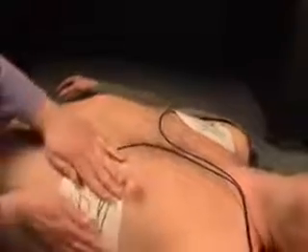If there is poor pad contact to the patient, the AED will prompt you to press the pads firmly. The unit automatically checks the connection of the pads to the victim and lets you know if the connection is bad. Make sure the pads are properly attached and not touching each other. If needed, reposition the pads and dry or shave the victim's chest.